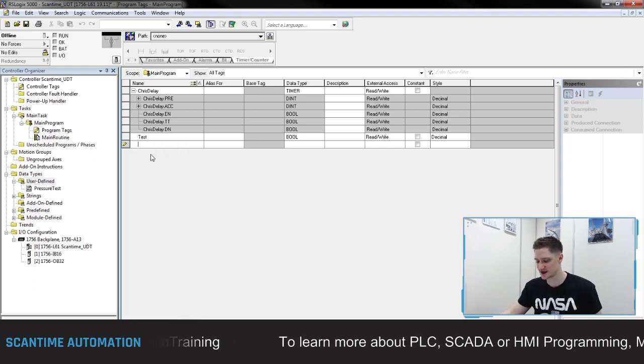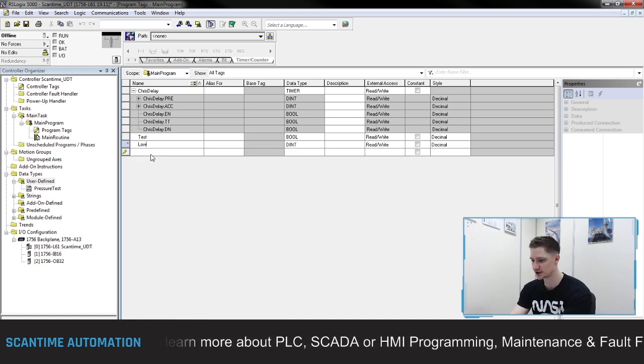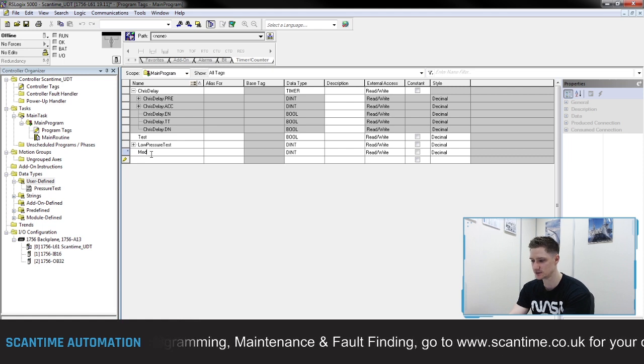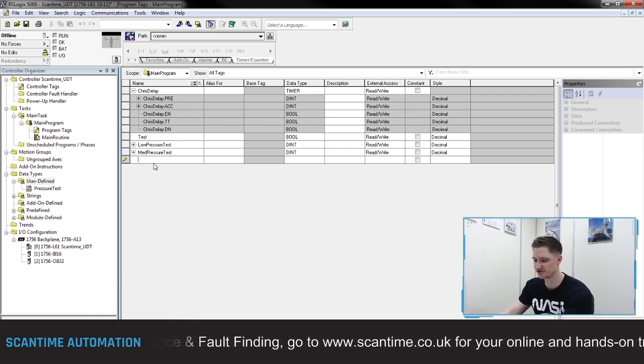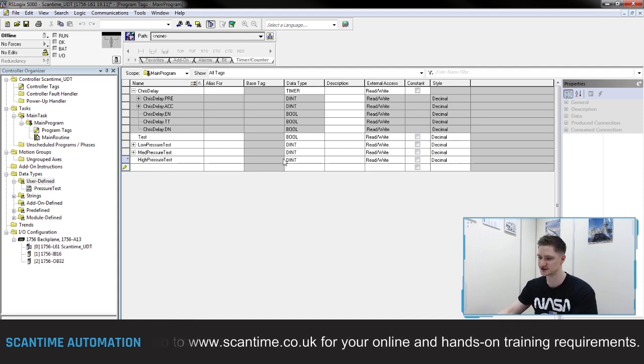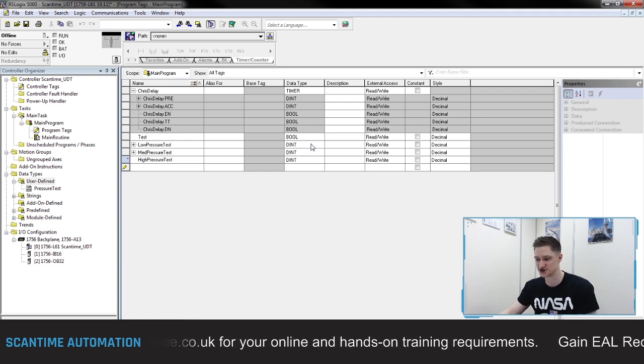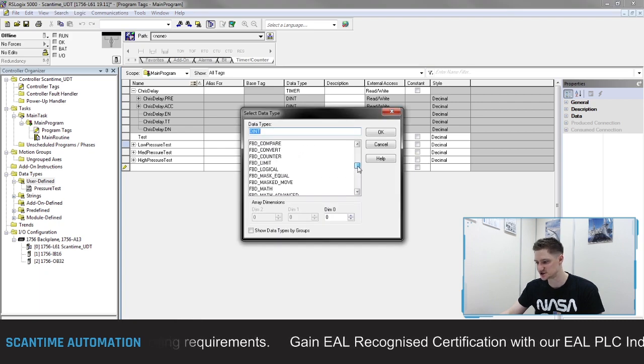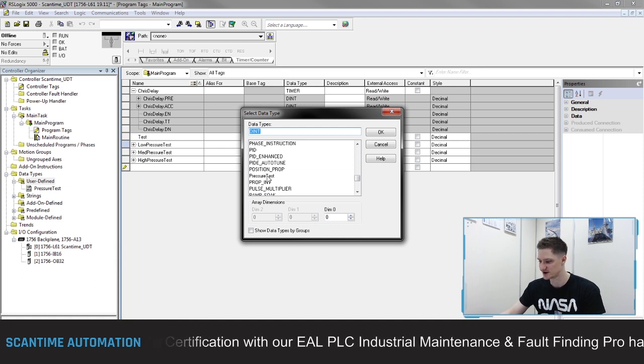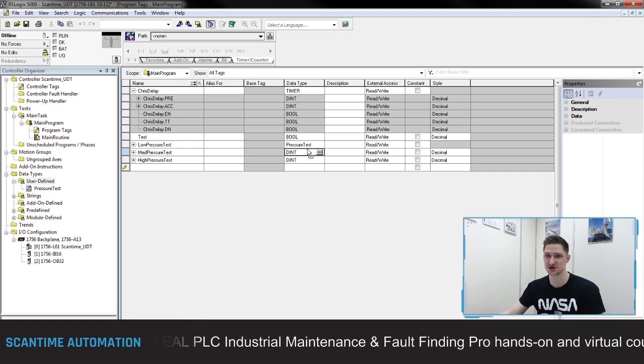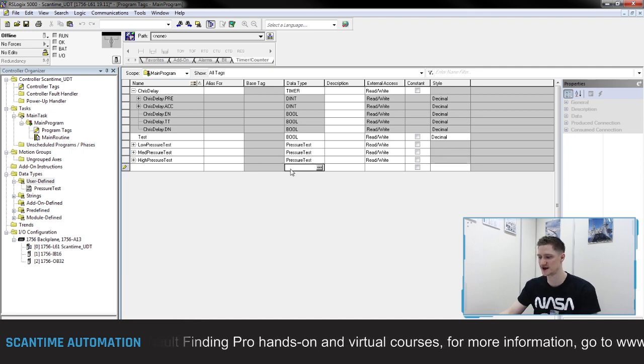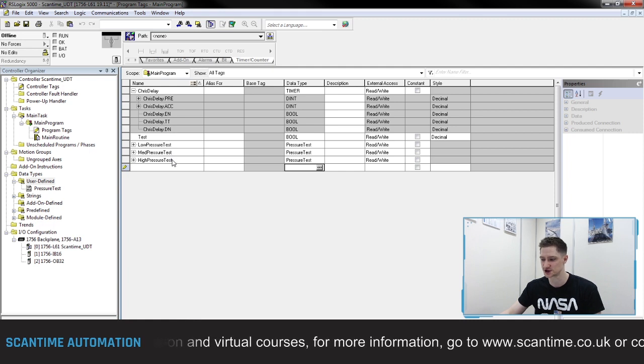Now if I open up my program tags and type in 'low pressure test', then 'medium pressure test', and 'high pressure test' — you'll notice they're pre-assigned data types as double integers. I'm going to change these. To change them, I click the three dots and scroll down the data type list to find near the P's 'pressure test' — that's our user-defined data type, our UDT. If I select that and say okay, then copy and paste for the other two, we are now using my UDT for my low pressure test, medium pressure test, and high pressure test.